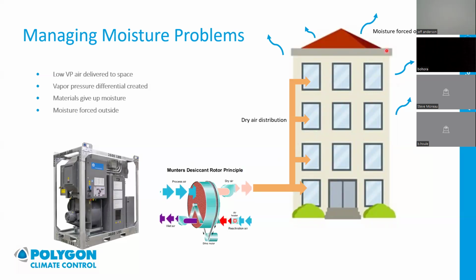On a construction site, there are commonly cracks or doors open, and that air just flows out naturally. We just create a slight positive in the building to force that moisture out. If it was a totally finished airtight building, then we would just open some windows. We could recirculate the air back through here. There's a few ways to go about it, but this is just the simplest way to look at it. We push in the dry air, slight positive pressure. It forces moisture out. The moisture leaves the building.